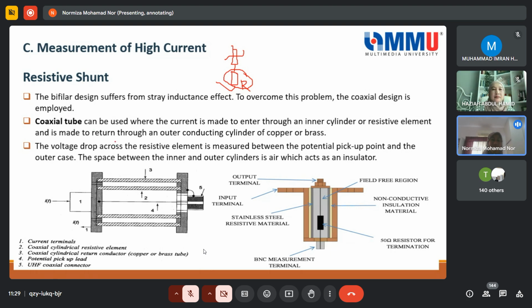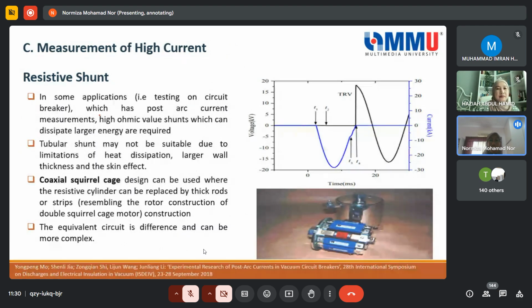So in the design, of course, they make it coaxial because they want to reduce the inductive effect. The material must be carefully selected to have high thermal capability, no inductive effect in terms of structure or design, and be able to give a very low value. That is the consideration when we want to measure high current. But that is the resistive shunt.